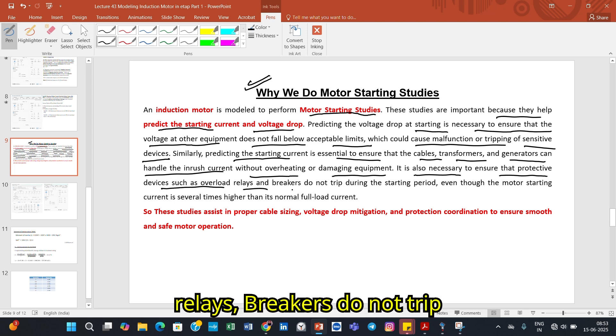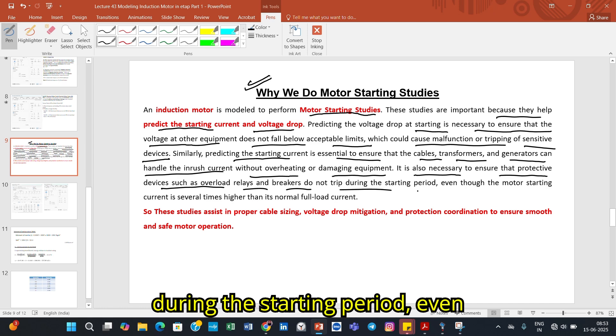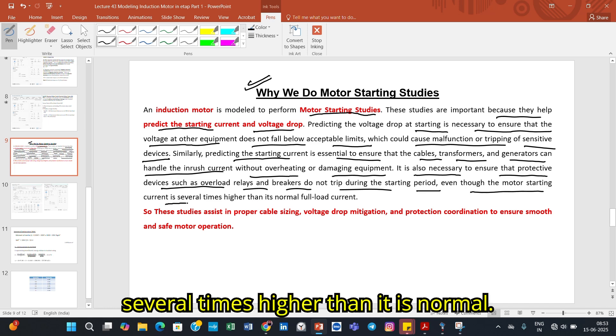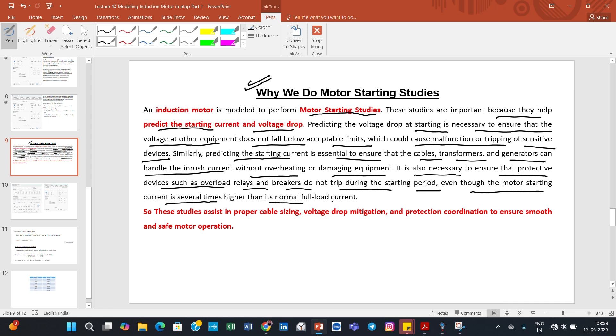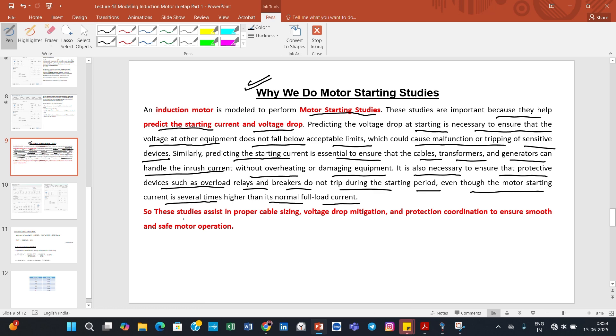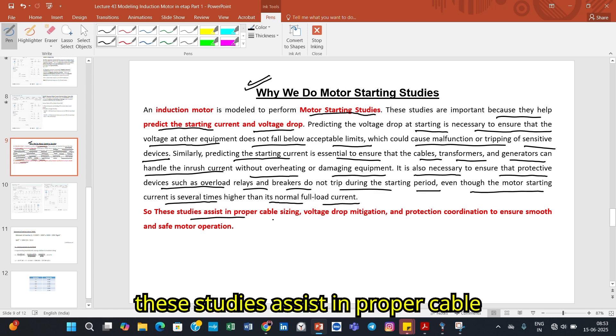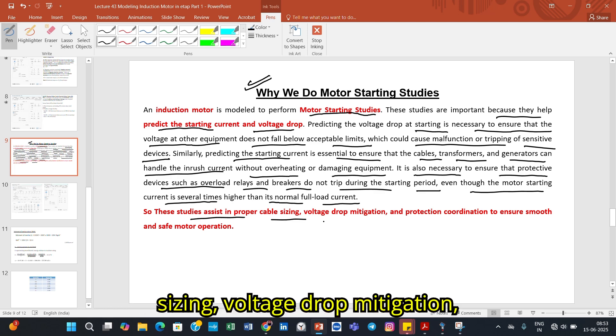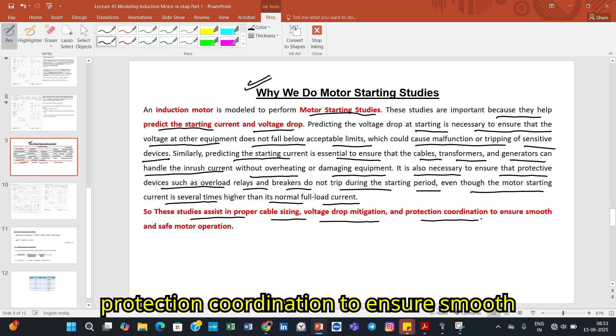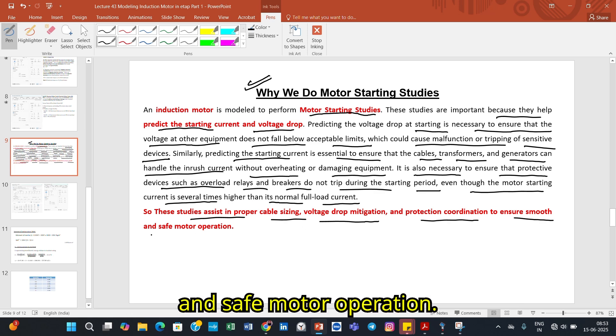It is also necessary to ensure that protective devices such as overload relays and breakers do not trip during the starting period, even though the motor starting current is several times higher than the normal full load current. These studies assist in proper cable sizing, voltage drop mitigation, and protection coordination to ensure smooth and safe motor operation.